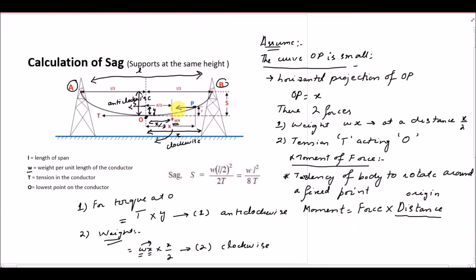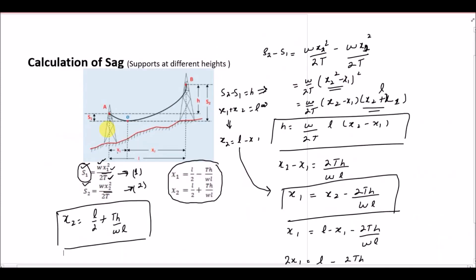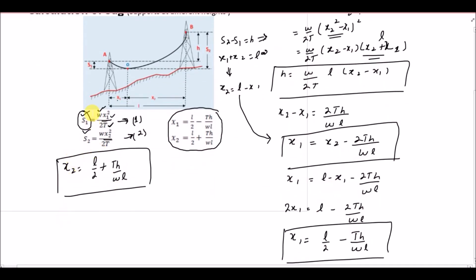To summarize: using the generic sag equation from the previous derivation, we defined two different sags — one from tower A and one from tower B. Since we didn't know the distance of the lowest point of the conductor from each individual tower, we first calculated x1 and x2 by subtracting s1 from s2, substituting h as the difference between s2 and s1, and L as the span. From there we can easily calculate the sag values.